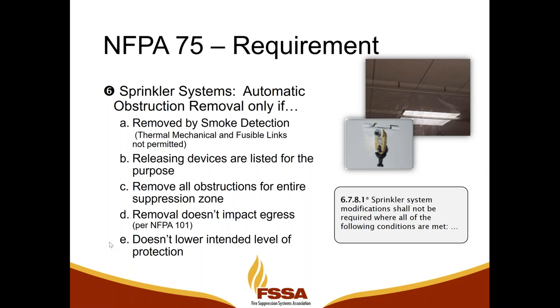And the code refers to NFPA 101, the Life Safety Code. So if your curtains, after they're automatically removed, wind up falling on the floor, and that's impeding a person's ability to egress the space, that's a problem. And then the removal can't lower the intended level of protection. That's the last thing that's written into the code. If the aisle containment materials fall away and they actually add fuel or combustibles to the fire that started, that's a problem also. So these need to be thought through if there's going to be automatic obstruction removal.